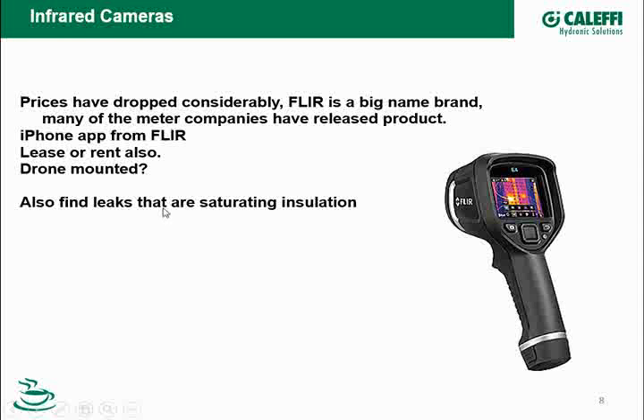Not only for finding temperature, but if you've got a leak in a pipe, maybe you've got that fiberglass insulation on all your piping and you've got a pinhole leak under there somewhere, you could point the infrared camera at that insulation and see that you've got a hot spot, because you've got a leak that you might not even know is underneath that insulation.